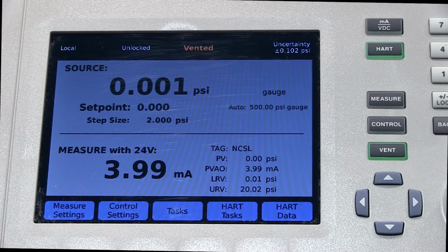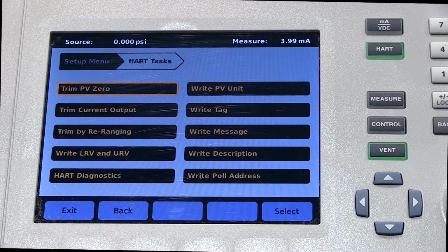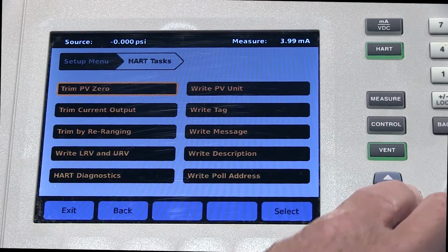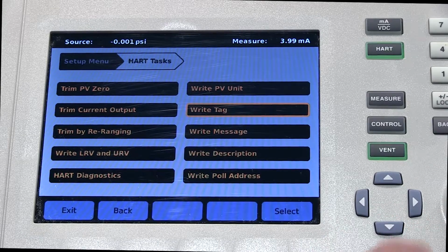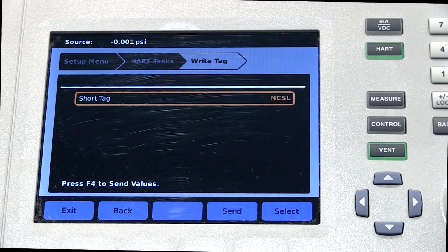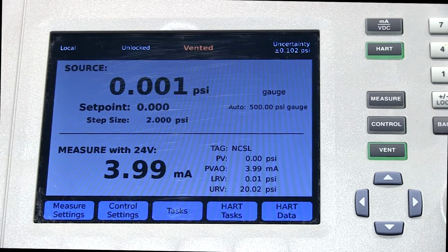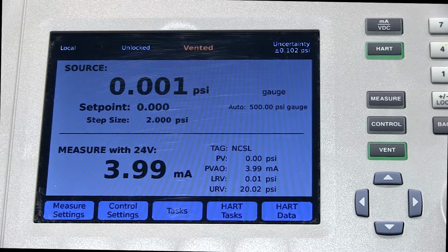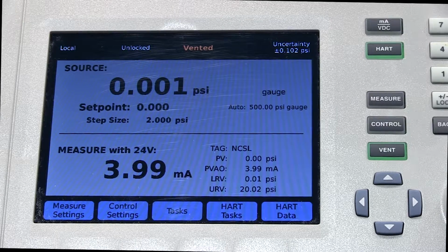Over here under HART Tasks. So these are some trim 0 values, either the current value or the process variable value, change the tags. And perform a lot of the normal maintenance routines for HART units. It doesn't replace a full HART communicator, but it does many of the tasks that would be needed in a calibration lab or instrument shop.